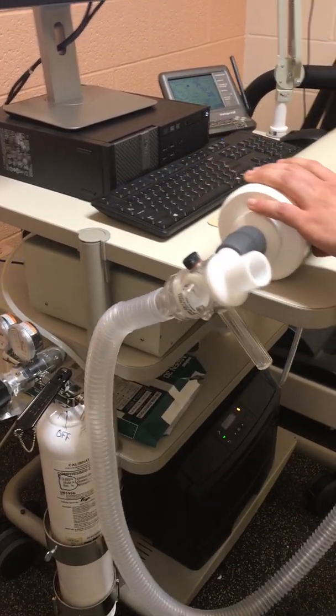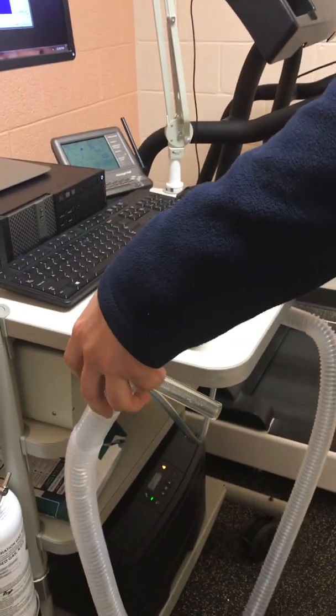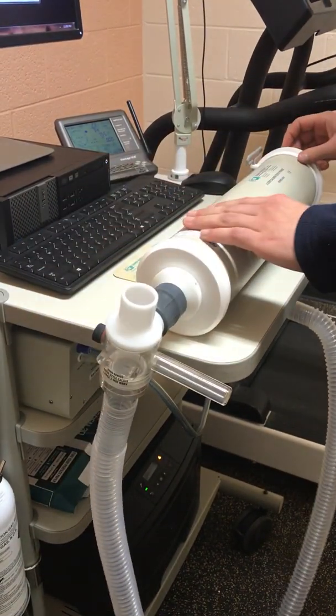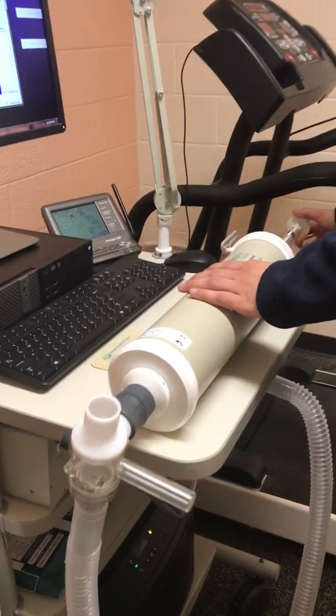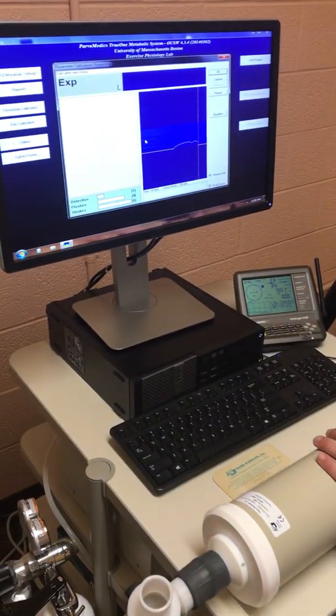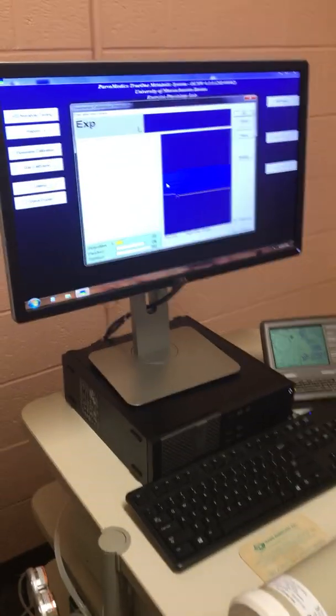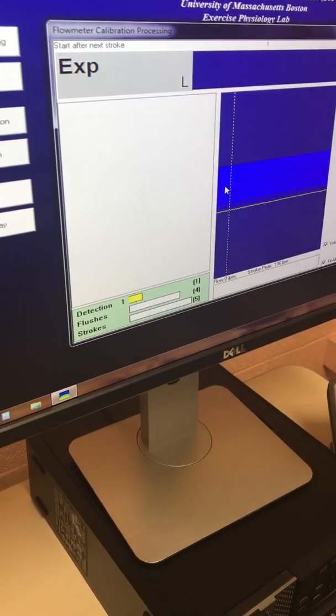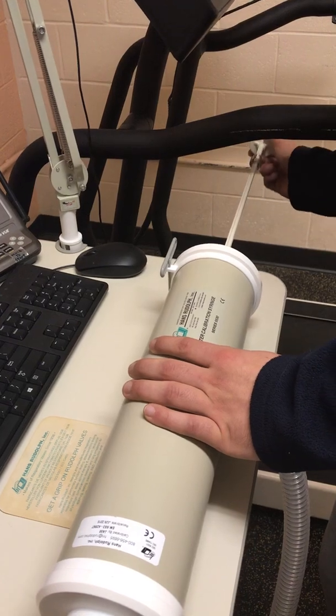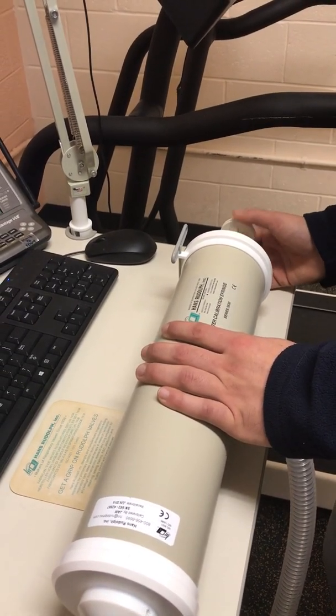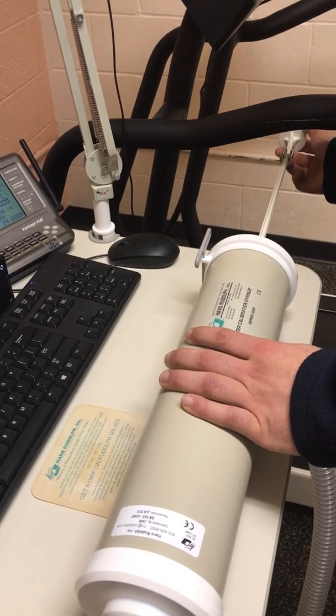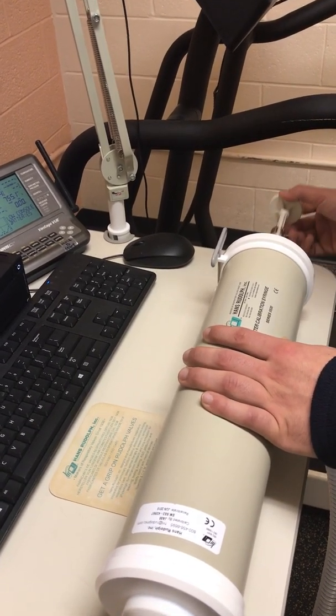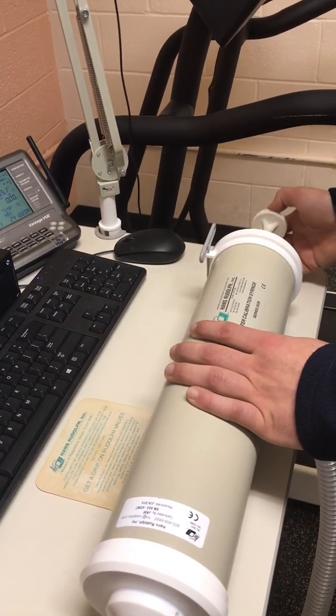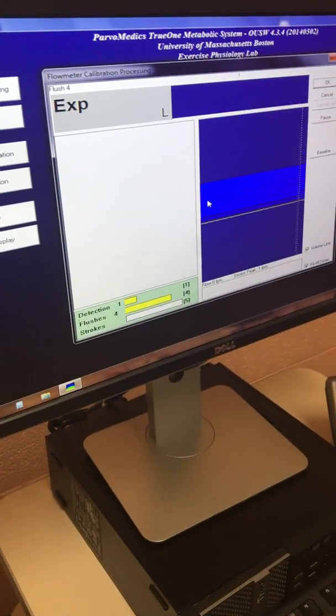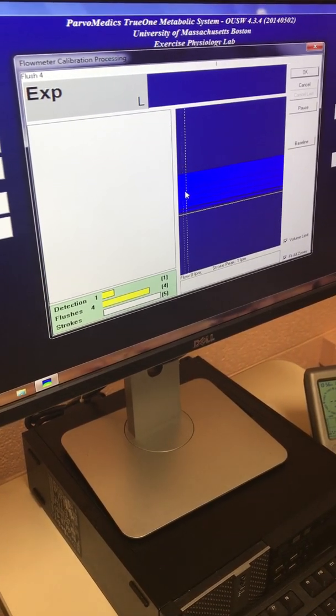And so the first thing that we have to do is a detection. Make sure that this is steady on the counter. And the first plunge is a detection. So we're going to pull the syringe fully out and insert it fully in. And then we're going to do 4 flushes. And these are synonymous with someone breathing. And so this is also a 3-liter calibration syringe, so we know the exact amount of volume we're working with.